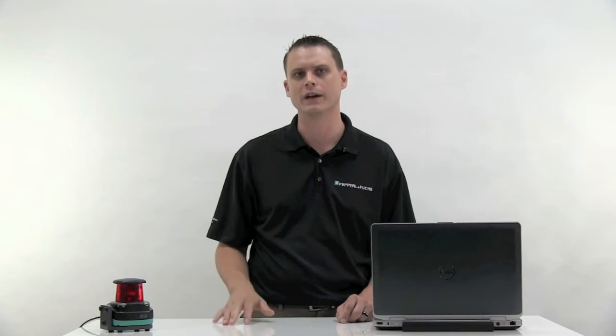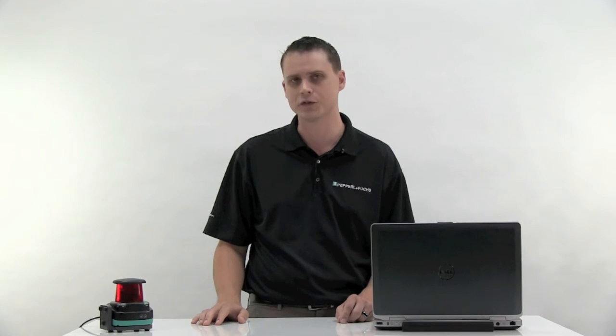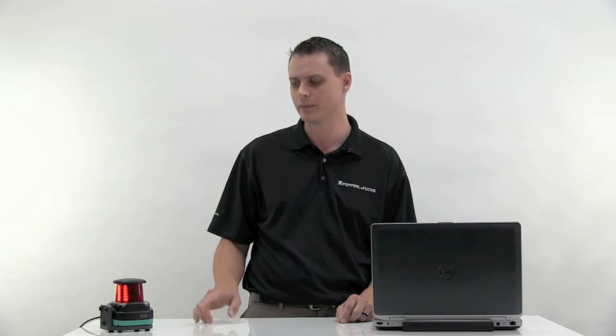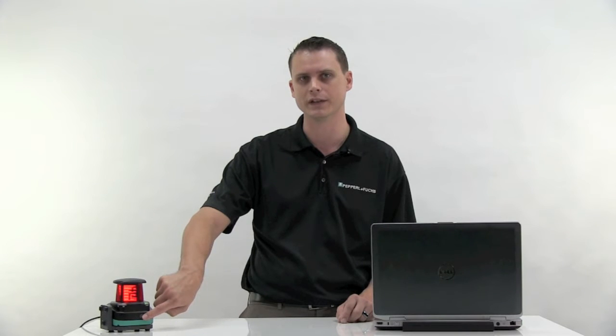Now, in order for the R2000 to acquire an IP address, there are three distinct modes built in. Number one being auto IP mode, number two is DHCP mode, and the third is static mode. Each of these modes can be accessed using the two push buttons on the front of the R2000 device.